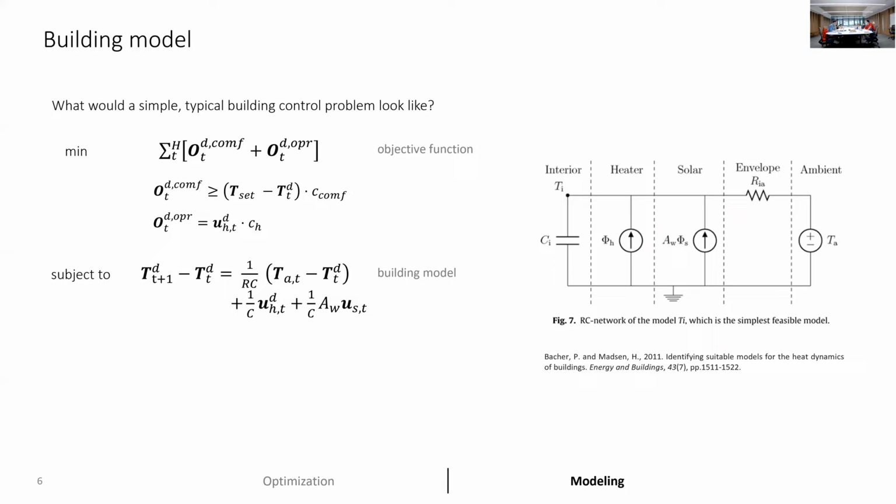So this is basically this model put into mathematics. Our state is our building's inside temperature, and the difference between two time steps, the variation basically in inside temperature, will be equal to the difference between ambient and building inside temperature, times 1/RC. We have heat inputs. So this is the decision variable here, the heat input. That's basically the value that the optimization problem is going to try to adapt to keep our building above a certain set point while minimizing its input because the heat costs.